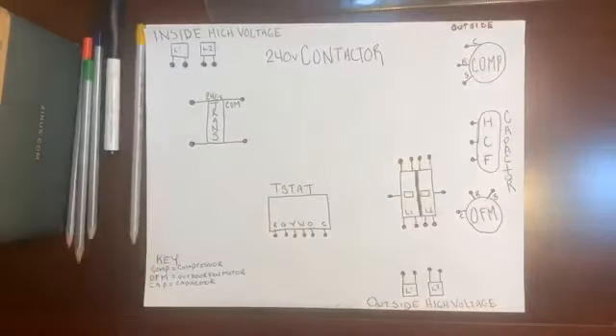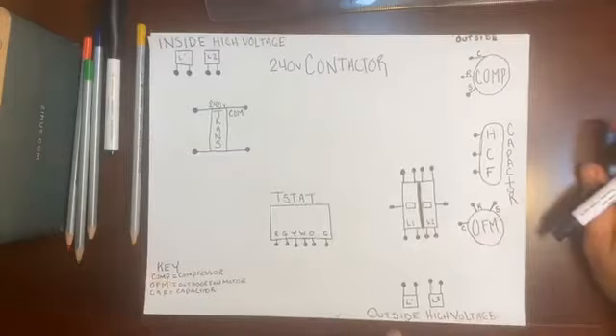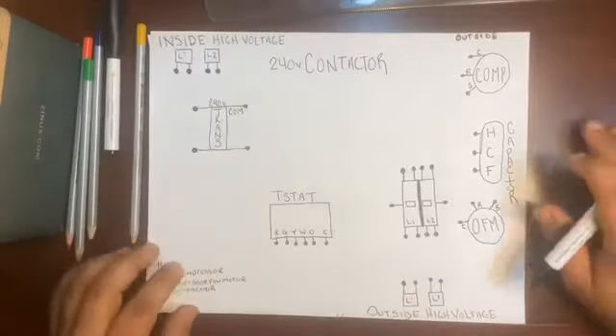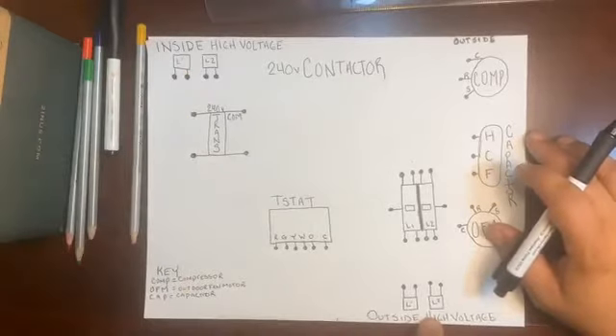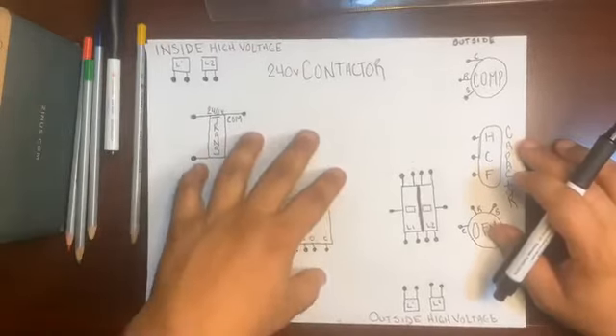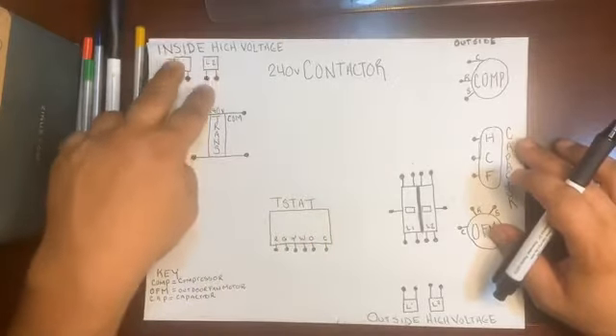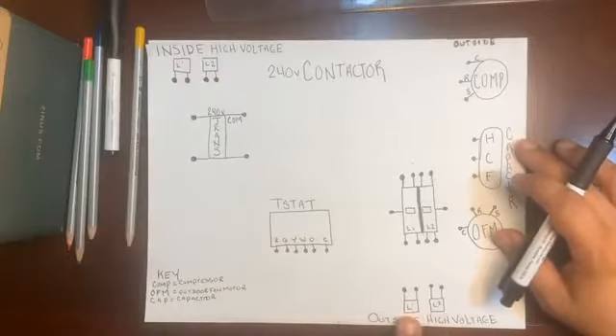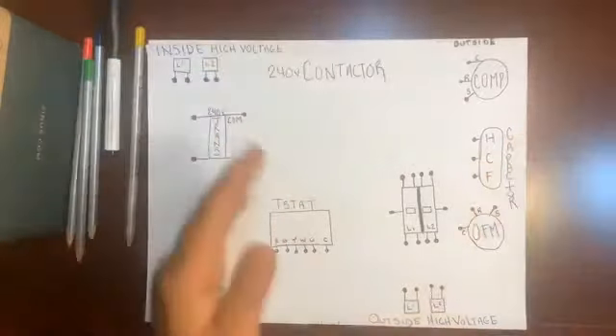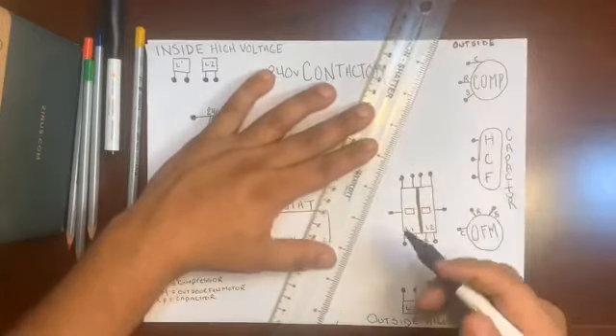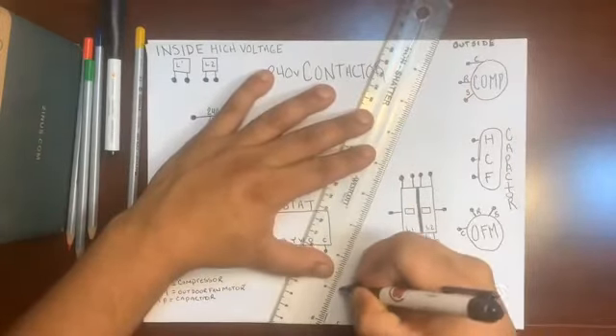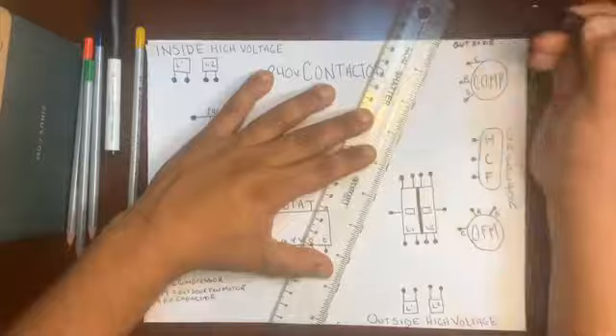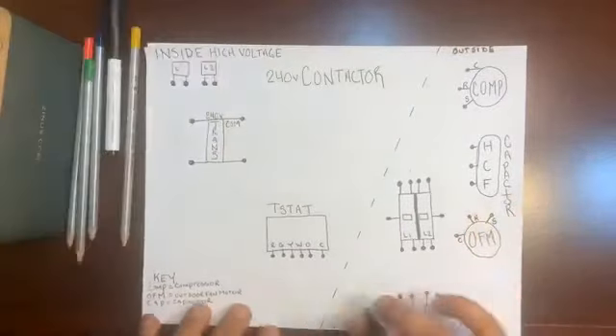So what we're gonna do today is we're gonna split our diagram. We have high voltage outside and high voltage inside, because there's a disconnect inside at the air handler and there's a disconnect outside at the condenser. So every air conditioner has two 240 volt circuits, one for the inside and then one for the outside. So let's go ahead and split our diagram. Very few wires go back and forth, so it's perfect to have these marked in. So you're gonna get a ruler and about every inch or so, you're just gonna make a hash mark. 9, 8, 7, 6, 5, 3, 2. So that way, your full diagram is split with an outside portion and an inside.